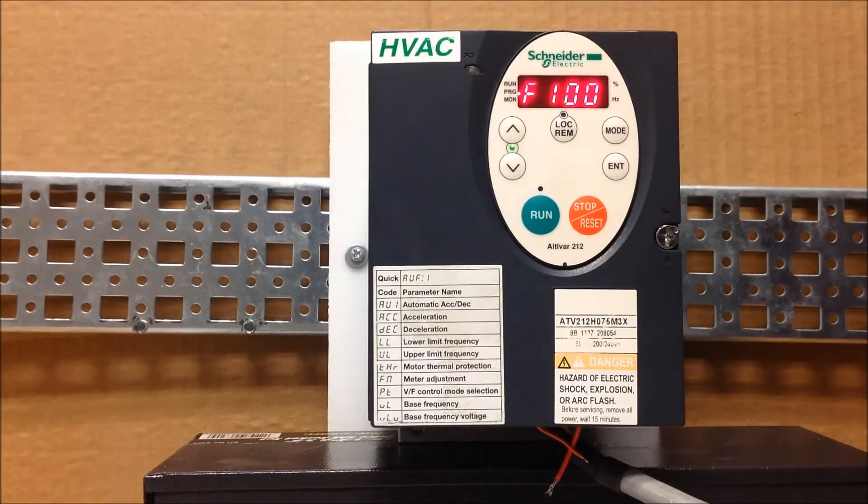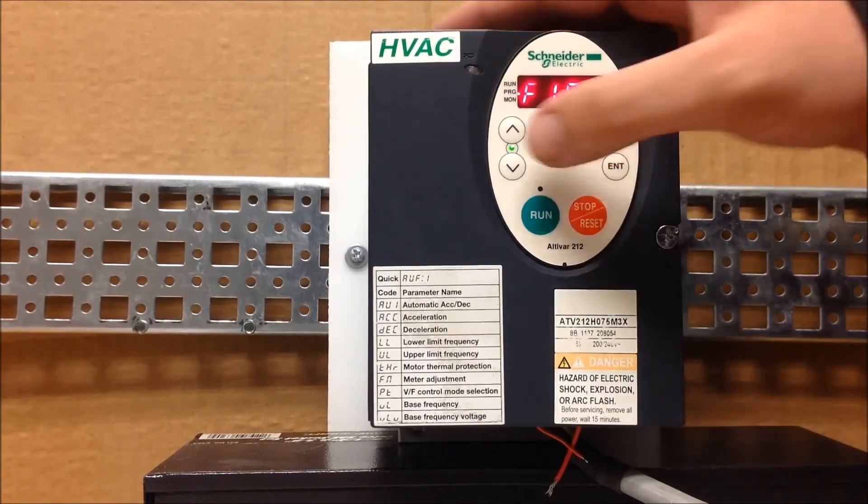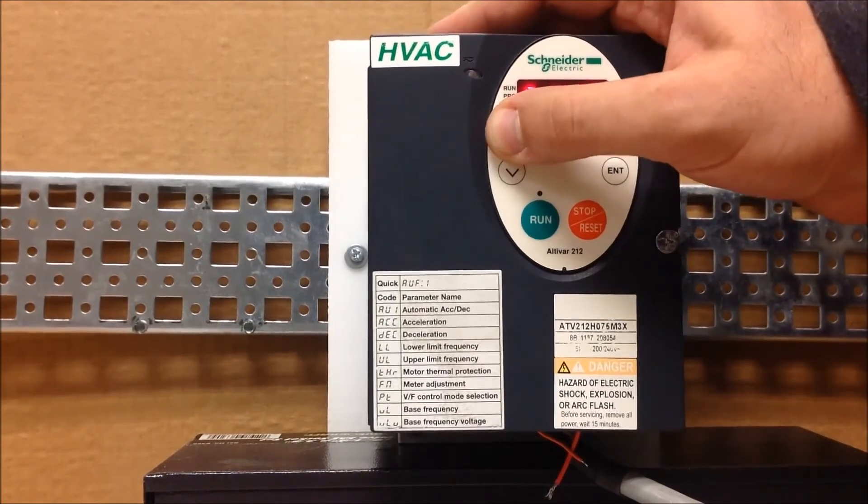As we mentioned before, we're going to go ahead and program the F112 parameter which is your R terminal as a reference switching function. You can also choose F113 for the RES terminal, up to you. You want to go ahead and set the F112 function to a 38 value.